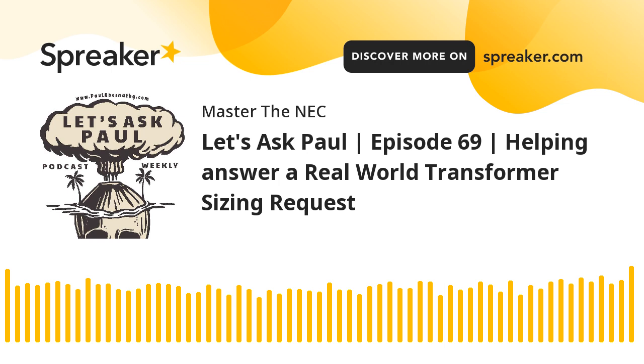You are going to, for example, need to have a service receptacle for this HVAC within 25 feet. So depending on what you're supplying on this secondary, maybe it's a 120/208 volt panel. And maybe at that point you need to put a panel instead of the disconnect just for the HVAC. Maybe you need to install a panel and then you'd be able to get load out of that to supply a 120 volt receptacle for servicing of this HVAC equipment, because you still have those rules you still got to meet. So, I mean, you've got a bunch of different options to think about. And by going to the 45 kVA, you get some more capacity out of it.